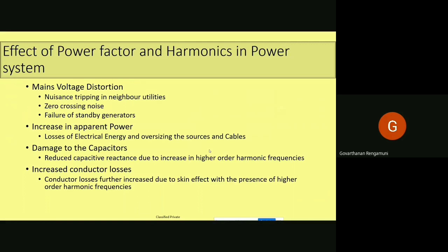So the neighbor utilities will face a distorted voltage input because of your pollution. Due to this, there will be nuisance tripping, zero crossing noise. If there is a voltage detector, then there will be zero crossing noise, and failure by standby generators.